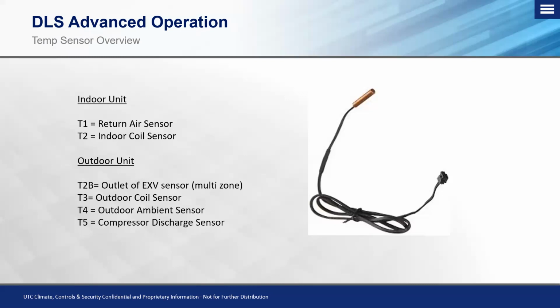In our outdoor unit, we have 4 main sensors. We have our T3, which is our outdoor coil sensor. We have our T4, which is our outdoor ambient temperature sensor. We have our T5, which is our compressor discharge sensor.